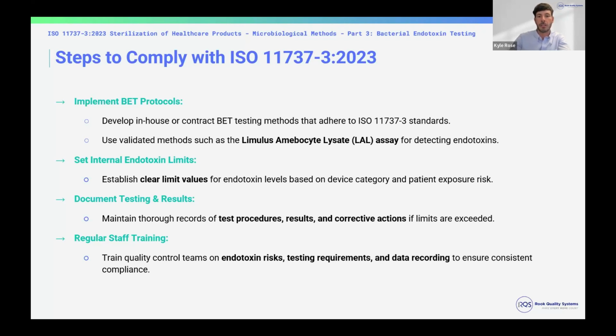So you do have initial endotoxin testing that's related to design verification, but you need to be doing ongoing endotoxin testing for manufacturing, whether that's for every batch or if it's more of a set time frame to do endotoxin testing based on your validated process. You have to do ongoing endotoxin testing to ensure that you're meeting the requirements of this standard and there's no endotoxins being allowed in your product that weren't destroyed during sterilization. So you make sure you're confirming that with these ongoing test results.